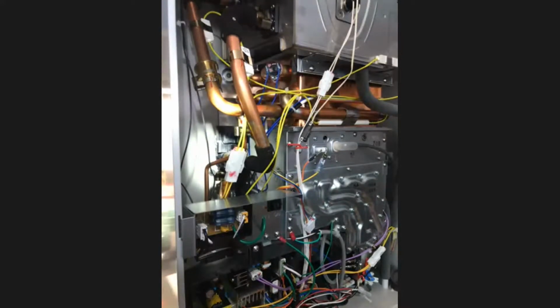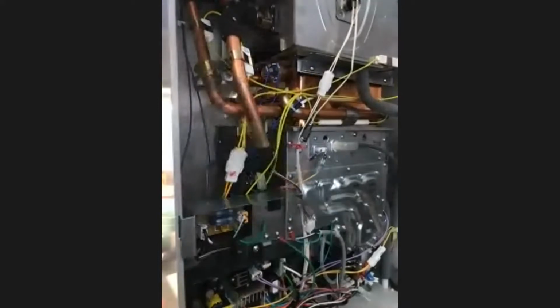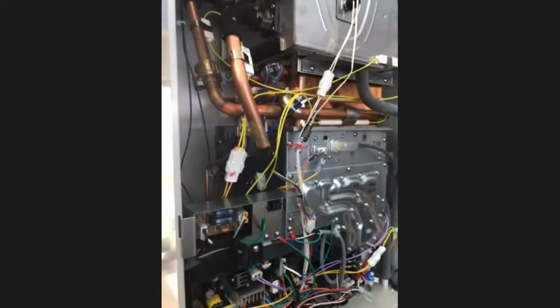That's the bypass valve. What it's doing is it can divert some cold water into the outlet water. It looks at the outlet water temperature and can influence it by using that bypass valve to divert some of the incoming cold water, mixing it - almost working like a mixing valve right there inside the unit.